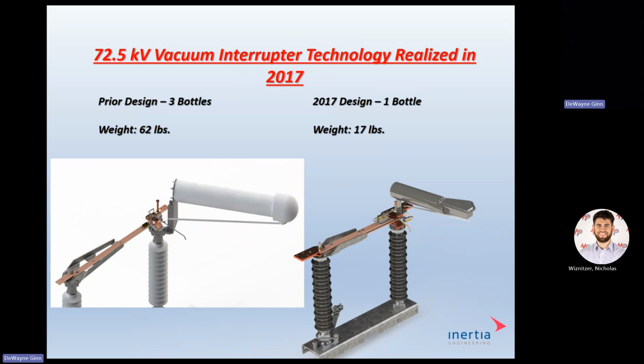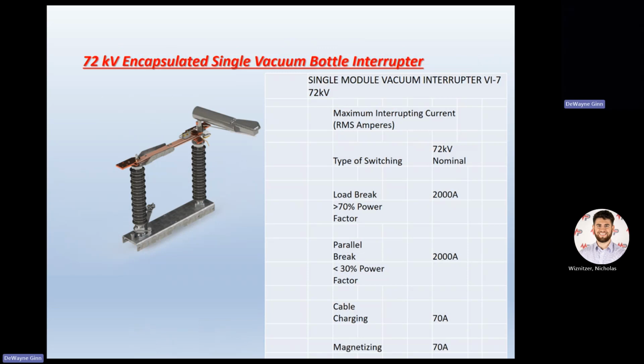The other side of it was the ratings on them are lower all the way around. The weight, 62 pounds on the cantilever action on the end of your switch versus 17 pounds. Very superior bottle all the way around, very superior interrupter. We now put these on all of our 72 kV switches. The ratings are superior on this. This is a 2000 amp bottle. Now our switch is only rated to 1200, but this is a 2000 amp bottle.